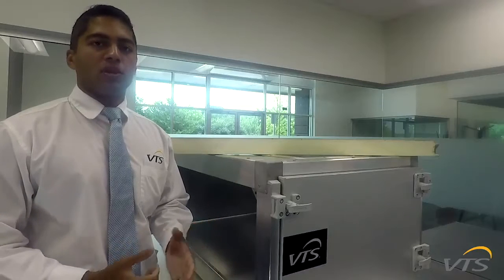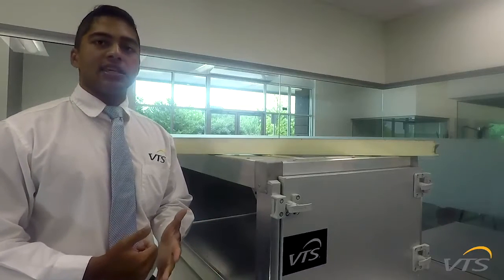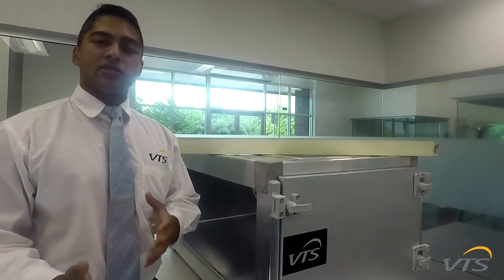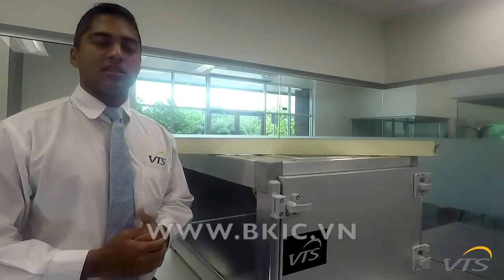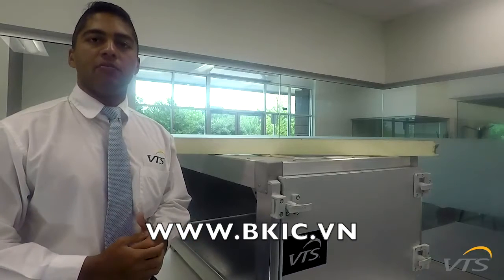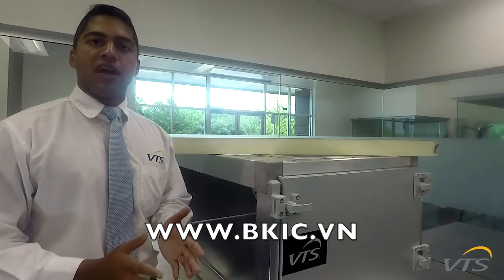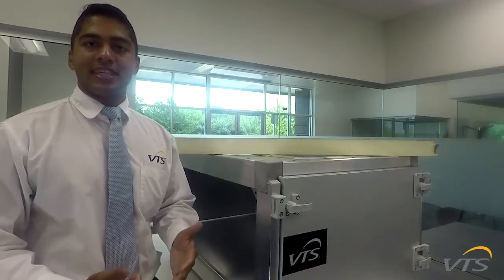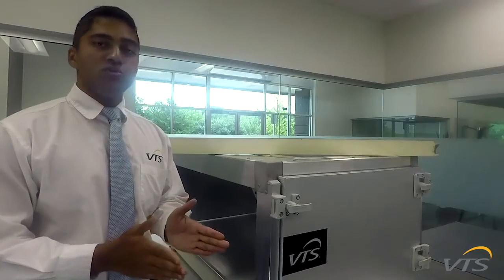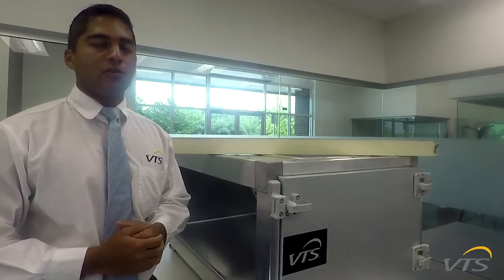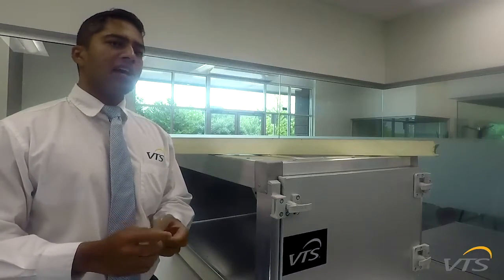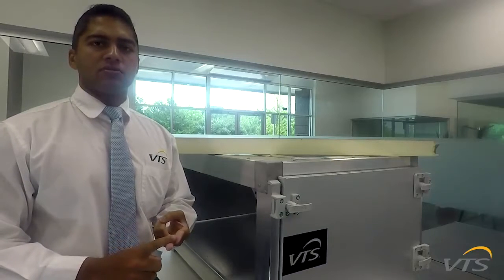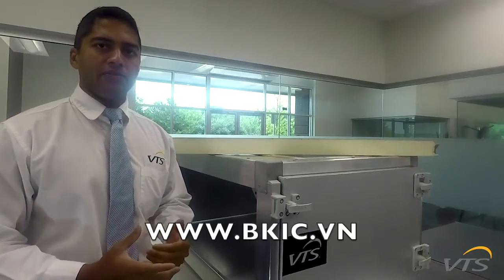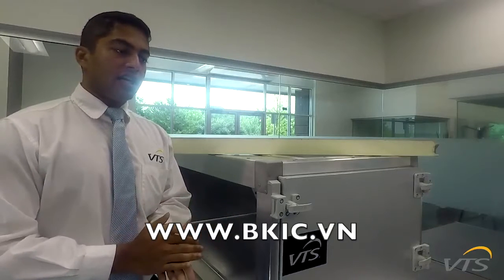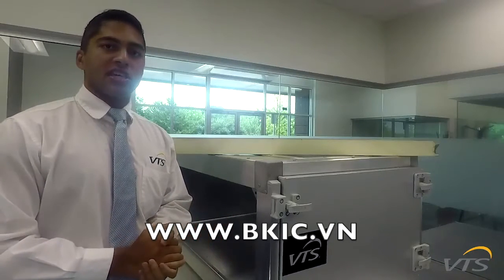And why is this important? So typically at a 2-inch casing design with polyurethane foam, you're requested for an R13 value. That's usually what's spec'd. Where does this R13 value come from? Well, let's go back to thermal, right? The R value of polyurethane foam is roughly 6.5 per inch. So at your true 2 inches, that's where you hit your R13 value. But if you think about it, if you have these air pockets and these air bubbles, you're not really hitting your R13 value, right? And even your casing could actually not be meeting the spec at certain sections because of those pockets and bubbles.